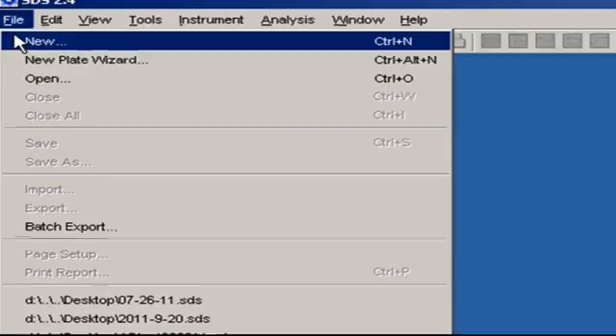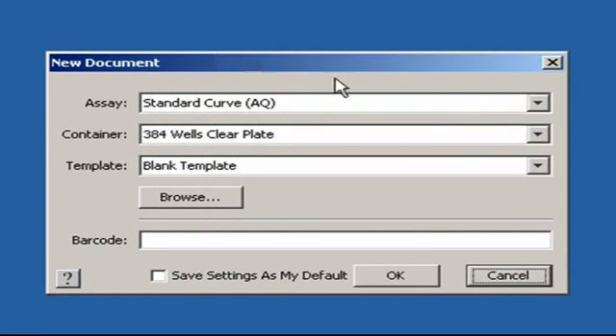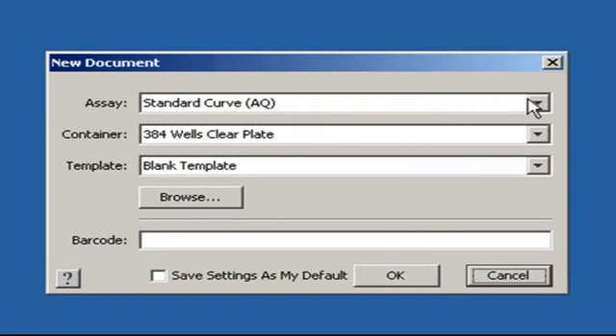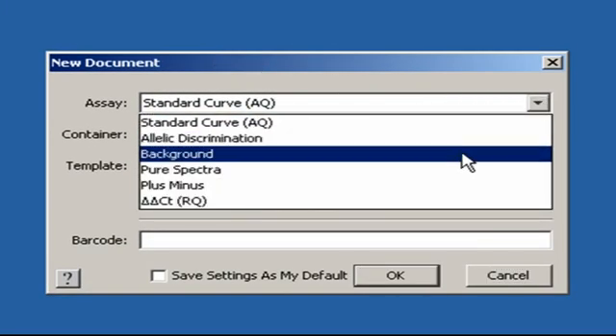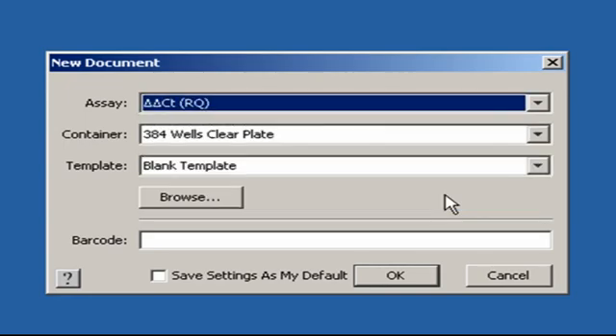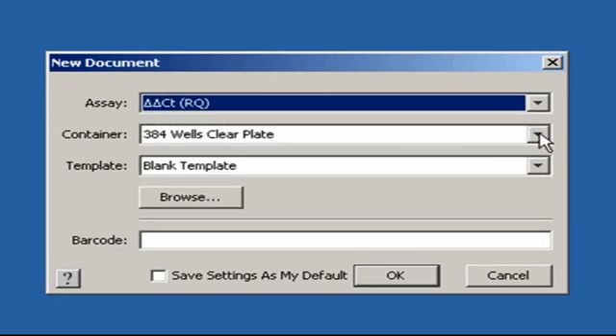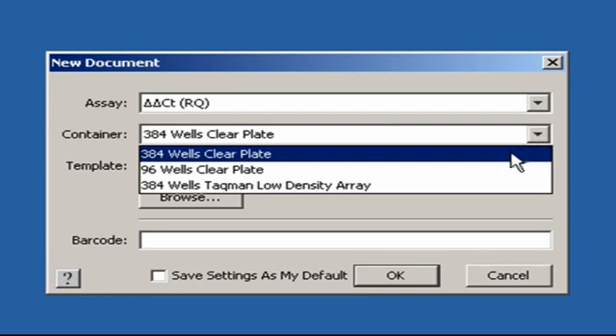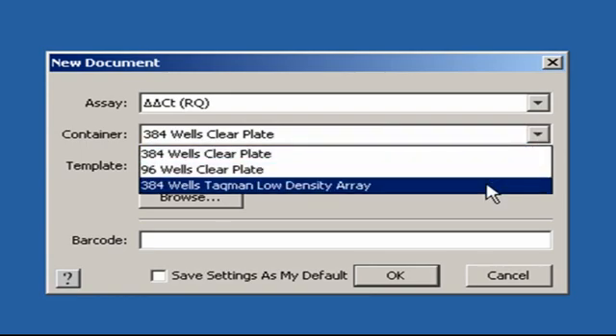And that's it for a regular setup. Just quickly, if I were using a TaqMan array product, the setup process would be a little different, as it was for the VS7. I'd still begin the same way, but instead of 96-well as my container type, I'd want to choose TaqMan low density array.